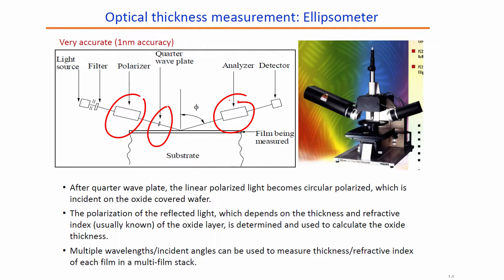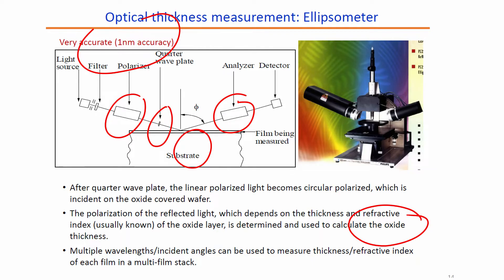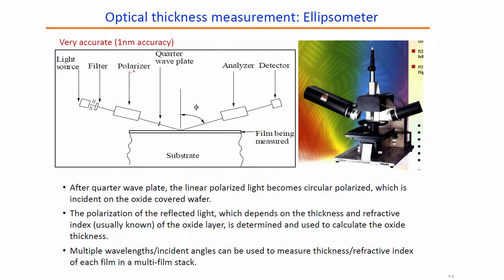What kind of analyzers are used for the ellipsometer? After the quarter wave plate, the linearly polarized light becomes circularly polarized, which is incident on the oxide-covered wafer. The polarization of the reflected light, which depends on the thickness and refractive index of the oxide layer, is used to calculate the oxide thickness. The ellipsometer is extremely accurate with an accuracy of about 1 nanometer. Multiple wavelengths and incident angles can be used to measure thickness and refractive index of each film in a multi-film stack. Your homework is to understand the role of the polarizer, quarter wave plate, analyzer, and what kind of detectors, light sources, and filters are used.